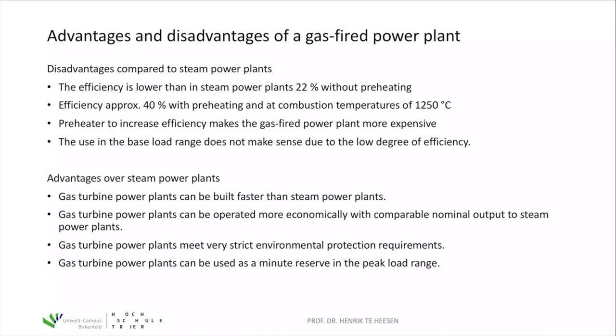However, the full load hours of a gas turbine are not that large, which reduces the economic efficiency of a gas power plant. Nuclear power plants achieve about 6,000 to 7,000 full load hours per year; coal power plants achieve 3,000 to 5,000 hours per year. A gas power plant typically has only about 1,000 to 2,000 full load hours, which makes the system more expensive per unit of electricity, as these plants are used to fulfill peak load rather than base load.